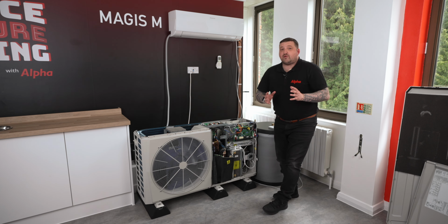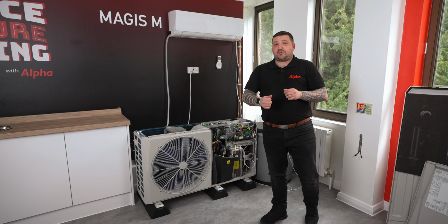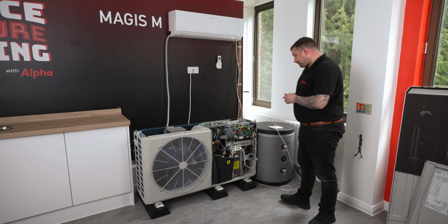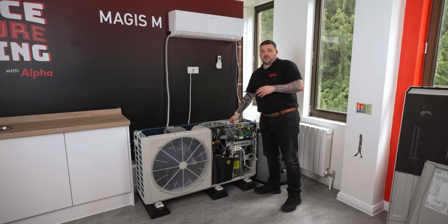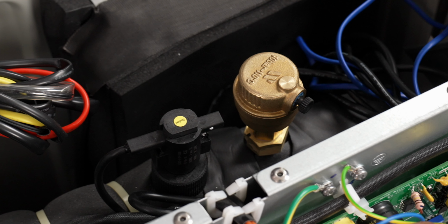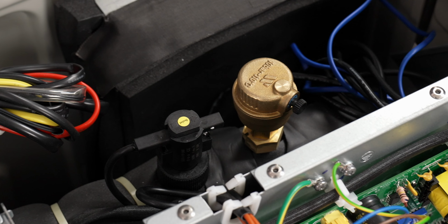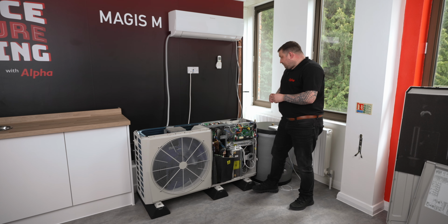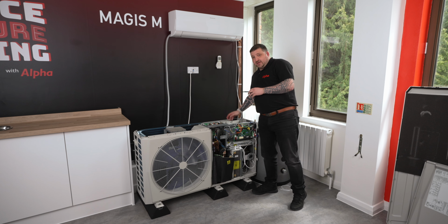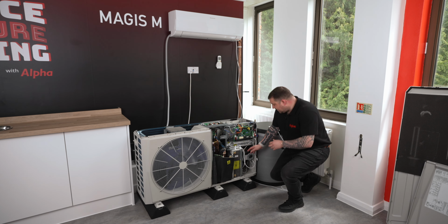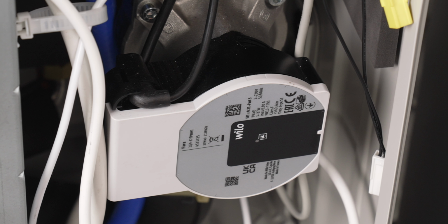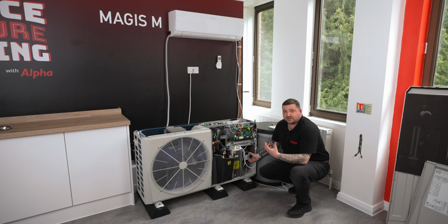Now, we spoke about some moving parts inside this heat pump compared to our hybrid and hydro range. They are the following. There's a flow switch inside the heat pump. Secondly, one of the good things is we've actually got an auto air vent inside the heat pump, which is great for trying to get rid of air. We've also got an expansion vessel, a heat exchanger, and we've also got an 8.5 litre pump. This is great for the primary section of the heat pump, for pumping the water to the buffer, which means we only need a pump post-buffer again to take the water out of your radiators.